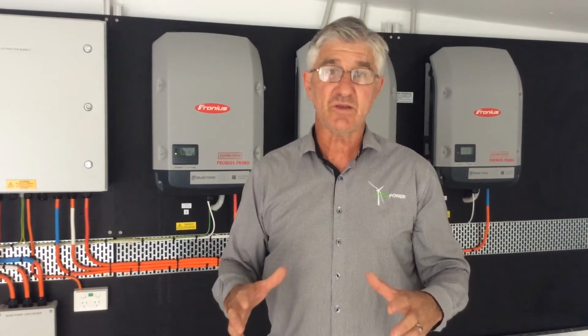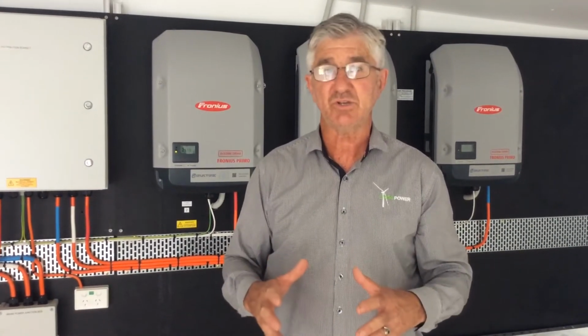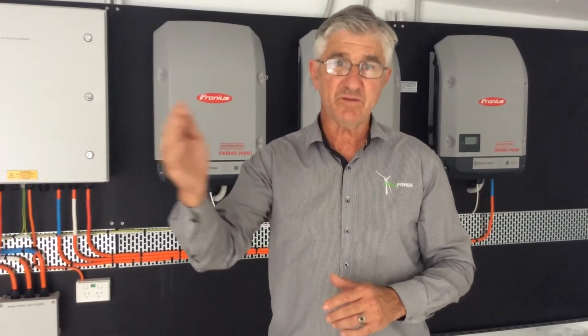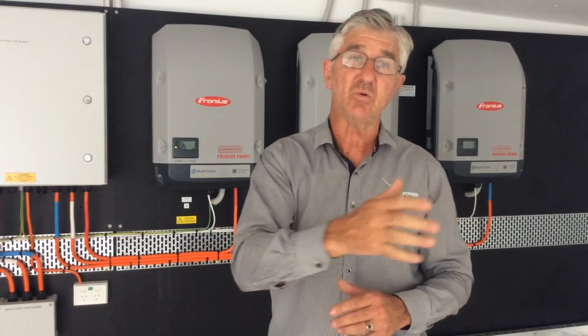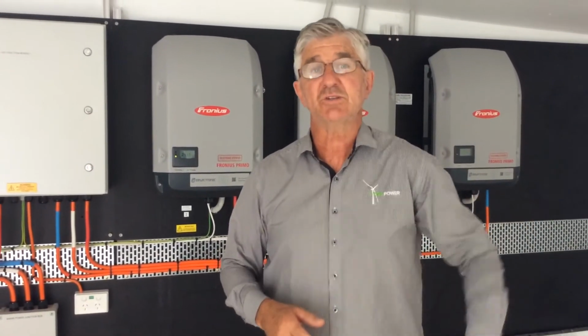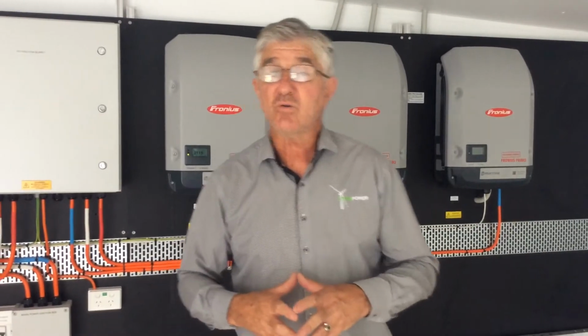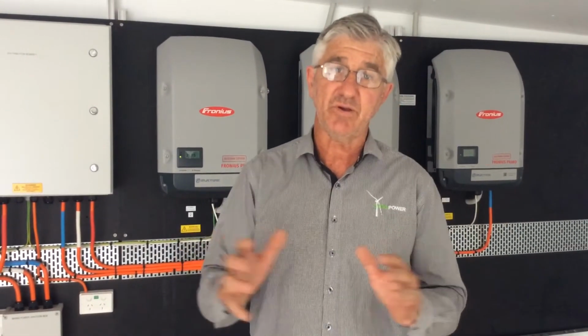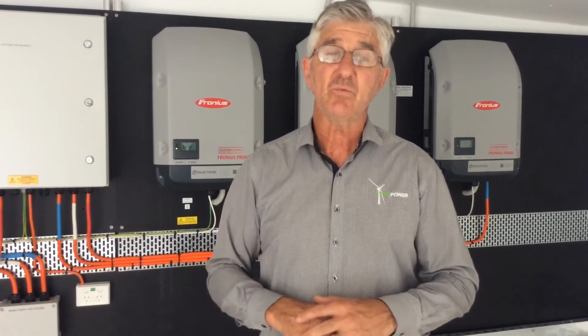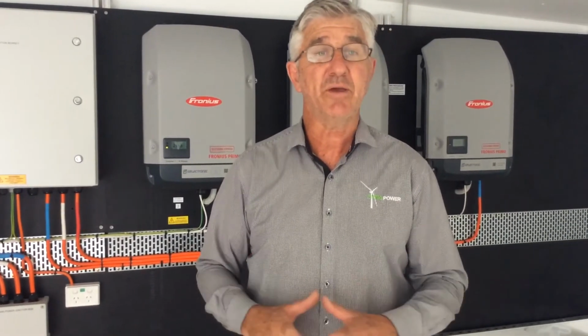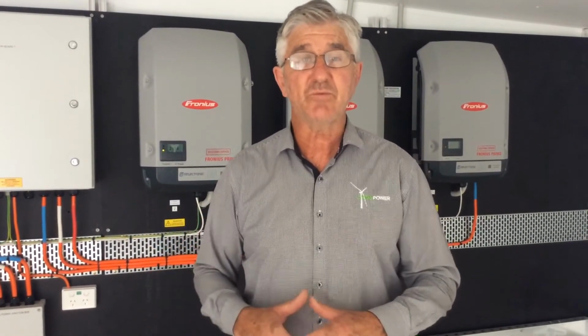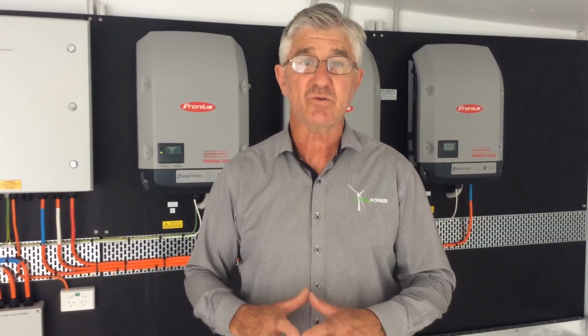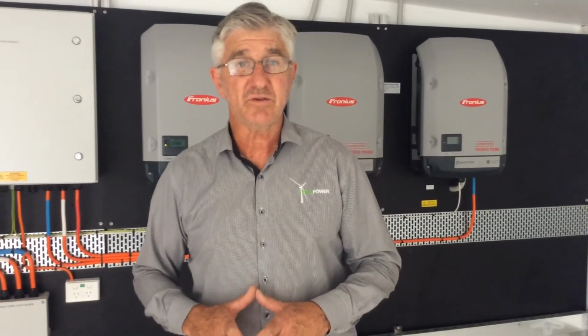So this is a really good example of what we would call grid augmentation, where it's too expensive to change the local cables, it's too expensive to change the local transformer, and in fact the local supply authority may not even have the capacity to supply the farmer with the type of power that he's after. But this will do the job very nicely for him at a much reduced cost. Should do very well here in central New South Wales.